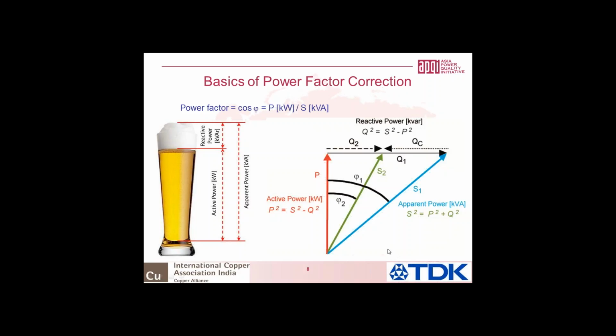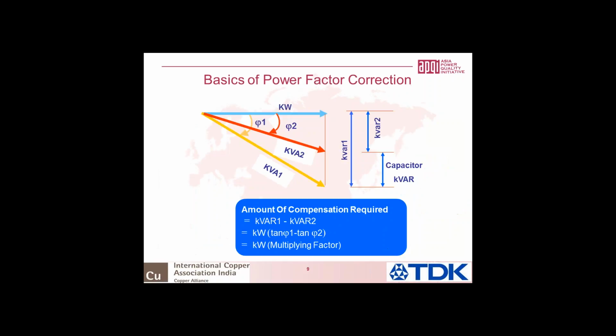And this again is a very classical equation where we won't spend much time on how to compute the amount of compensation required. So kVAR1 is the total reactive VAR required for the load. Then we have the capacitive VAR, and kVAR2 is the net reactive VAR required after compensation. And the classical equation can be very simply derived: the amount of VAR required is kilowatt into (tan phi1 minus tan phi2). This is again true as far as balanced sinusoidal conditions are concerned.